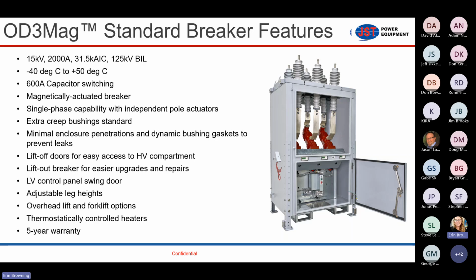So we're talking about a 15 kV breaker. Our portfolio is today 15 kV only. Rated up to 2000 amp continuous current and up to 31.5 kA interruption. The bushings are extra creep bushings rated for 125 kV BIL.